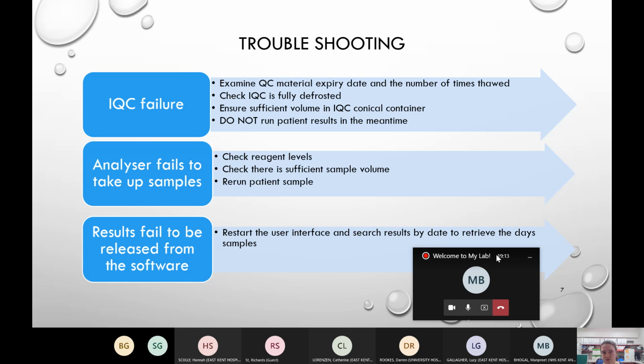And another kind of error that would sometimes come up would be that the analyzer wouldn't take up the sample properly. This could have been because sometimes the reagent levels weren't high enough, and because we didn't have enough reagent, it couldn't run the sample through the capillary tube properly, and so it couldn't create the bands and couldn't create results. Sometimes as well, there wasn't enough sample volume. That could be an issue. Or sometimes the sample probe just missed a part, it didn't pierce through the lid properly. And if that was the case, sometimes we just had to rerun the patient sample and see if it would work the second time around.